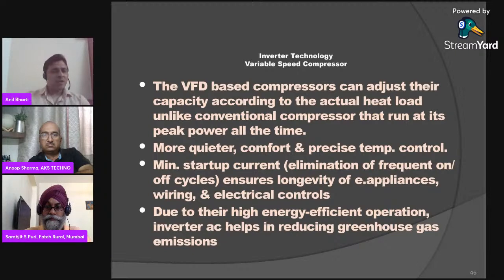अब बेसिकली हमारे जो ट्रेडिशनल एसी में क्या होता है, उसका जो कंप्रेसर है, it is coupled with a motor which cannot reduce its speed, it runs at a fixed speed. ठीक है, तो उसमें क्या होता है कि जब आपके रूम में लोड या कूलिंग लोड कम हो गया, तो हमें उसी प्रोपोर्शनली we want कि हमारा जो कंप्रेसर है उसके आरपीएम कम हो जाए और जो रेफ्रिजरेंट का जो फ्लो है वो भी कम हो जाए, तो एक इक्विपमेंट अपने आप ही उसकी कैपेसिटी डाउन हो जाए। लेकिन जो हमारे कन्वेंशनल एसी होते थे पुराने वाले, उसमें ये वाला प्रोविजन नहीं है, they cannot accommodate any such type of settings.